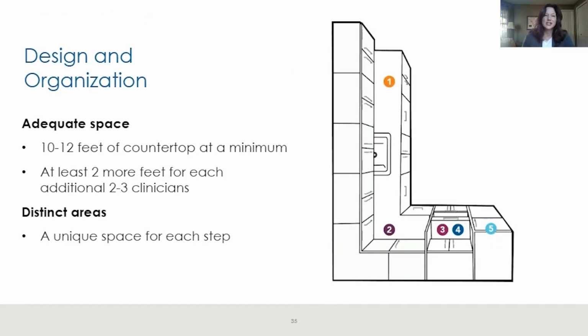So what does a good space look like? In a perfect world, or if we're designing a new build or want to increase efficiency in our sterilization area, we need about 2 feet for each of the 5 steps—approximately 10 to 12 feet of countertop at a minimum. This example shows an L shape, but you could have a U shape or a galley shape, and that's fine. But at least 2 feet for each step.